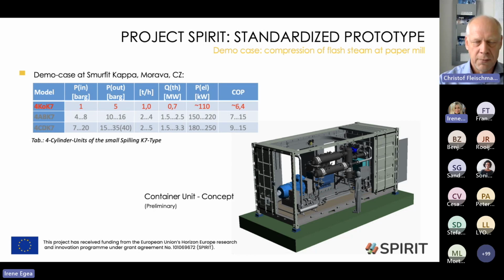And what we are installing here at Smurfit Kappa in the Czech Republic is a compressor for compressing flash steam from a condensate expansion, available at about 1 bar gauge, and it shall be compressed to 5 bar gauge so that it can be used directly again for the drying cylinders. This 4-cylinder unit manages about 1 ton per hour of steam flow, and with about 110 kilowatts of electrical power consumption, finally a COP of about 6.4 results.